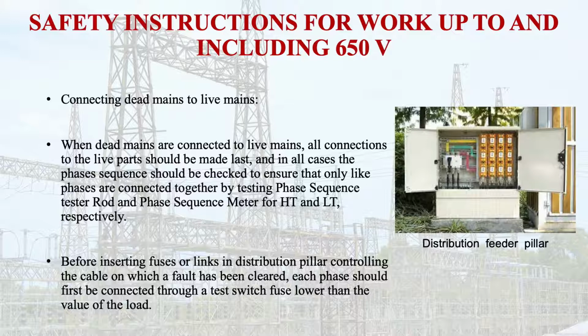Here, what is this distribution pillar which is controlling the cable? In this figure you will get some idea: for example, the low voltage distribution feeder pillar can incorporate the isolators, contactors, heaters, fuse boards, MCB or HRC fuses, circuit breaker, fuse gear, and cable terminations.